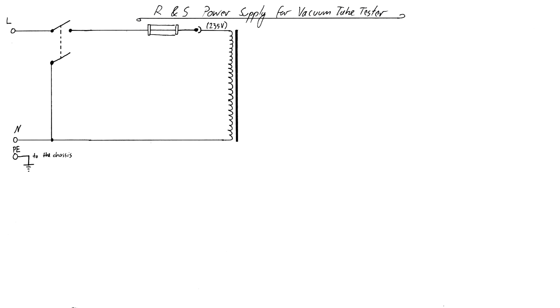Via the on-off switch and a fuse, the transformer's primary winding is connected to the grid. In order to allow operation from different line voltages, the primary has 3 additional taps. By inserting a fuse in the 4 different slots we have seen before, the transformer can be powered from 235 volts, 220 volts, 125 or 115 volt lines, while the secondary voltages stay always the same. A neon lamp and the little red fan is then permanently connected to the 220 volt tap. In this way, these 2 devices are always supplied with 220 volts, no matter from which line voltage it is supplied. The primary winding is thus also acting as an auto transformer here.